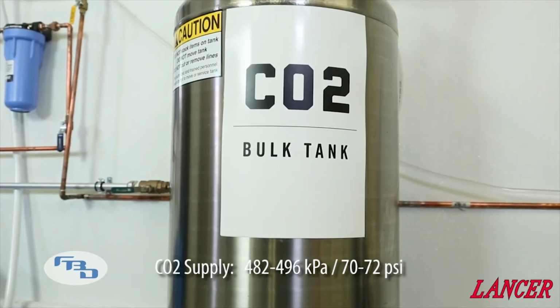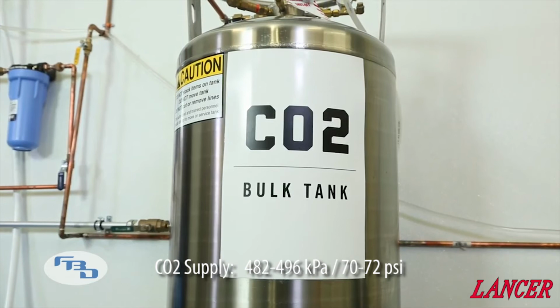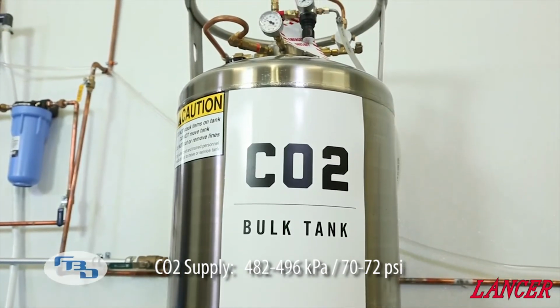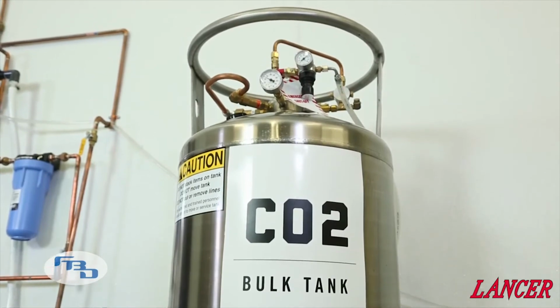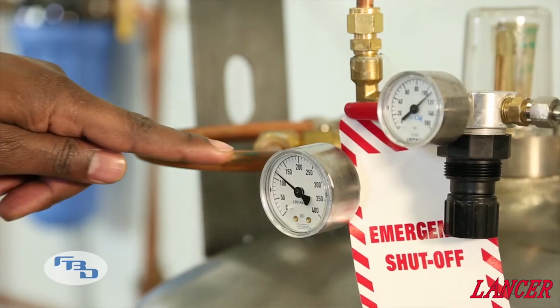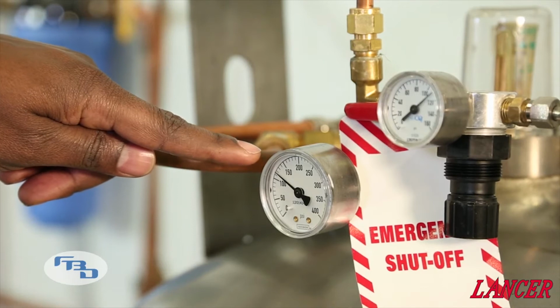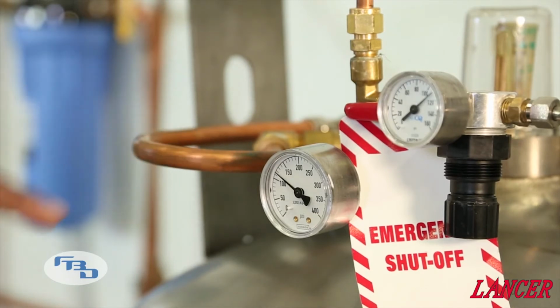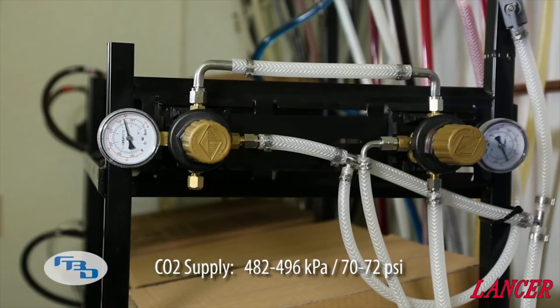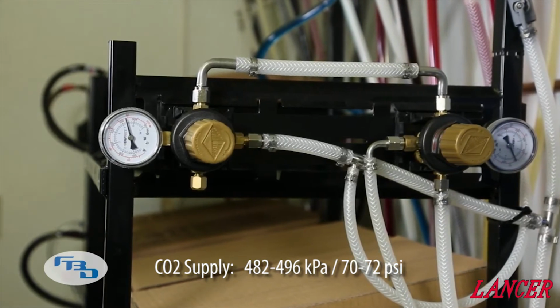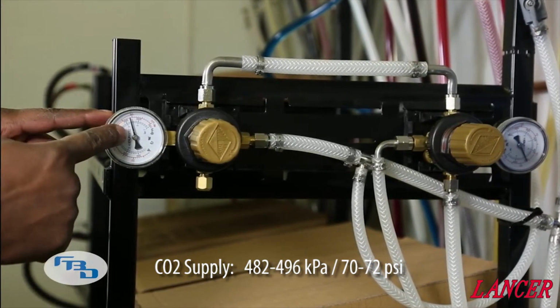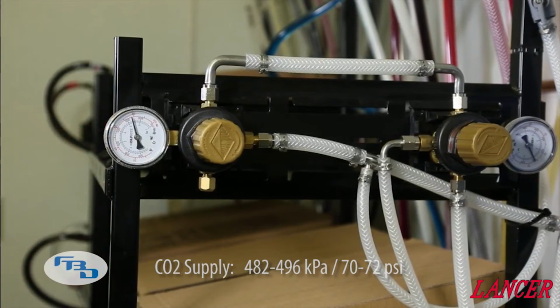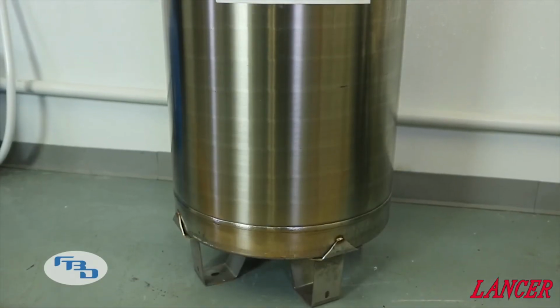The CO2 supply is to be provided by the customer and should have an available pressure of 70 to 72 psi. If a bulk CO2 supply is used, the pressure should be set at 115 to 120 psi, and a secondary regulator must be installed at the unit to reduce the pressure to 70 to 72 psi. As a reminder, CO2 displaces oxygen.